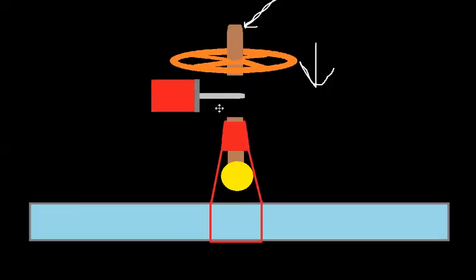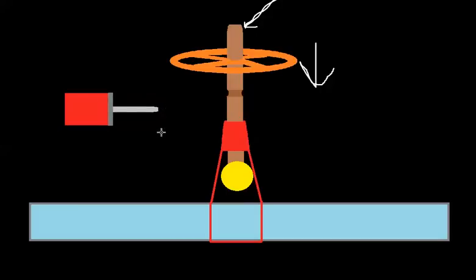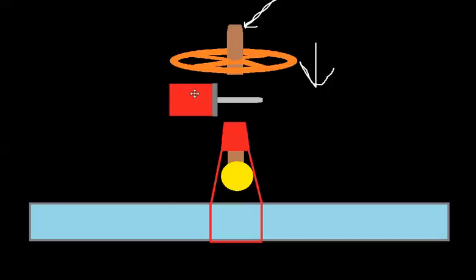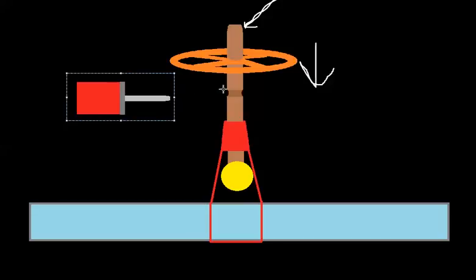So hopefully you can imagine this little arm would sit in this groove. And you calibrate the valve, the valve tamper, so that it's in a normal state. The contacts are in their normal state when it's positioned right in the groove here.